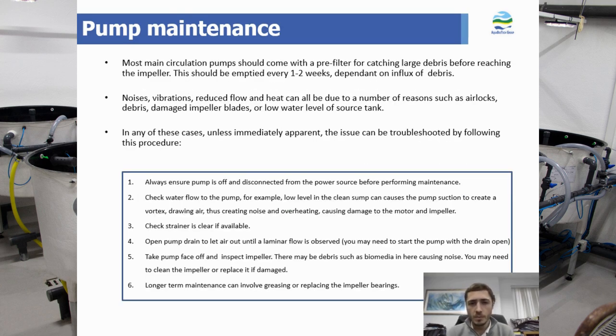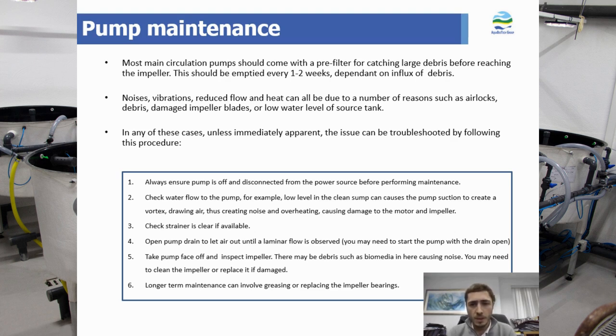Most main circulation pumps should have a pre-filter for catching large debris before reaching the impeller. This should be emptied every two weeks at minimum, but possibly every week depending on the influx of debris or your application. Issues with the pump can be spotted through noises, vibrations, reduced flow, and heat coming from the pump. This can be for a number of reasons such as an airlock within the pump or system, debris in the housing, damaged impeller blades, or low water levels of the source tank — such as if you're drawing from the biofilter sump, a reduced level will cause cavitation to occur. In either case, you can follow this troubleshooting procedure. Each pump will have its own procedure, which is a general guideline.